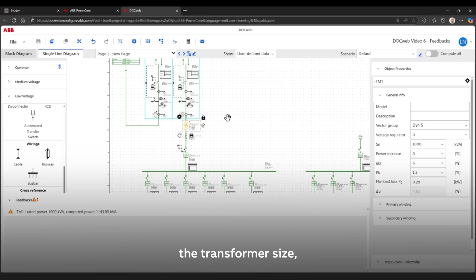If that's already set, then we need to look at your loading. In most single-line drawings, there's a diversity factor for each load. For example, if I click on this bus bar, it's set at a loading factor of 100%. But in reality, it won't be at 100% all the time. Even if you look at IEC 61439, the standard for switchboards, it states that with a certain number of outgoing circuits, a demand load factor can be used.